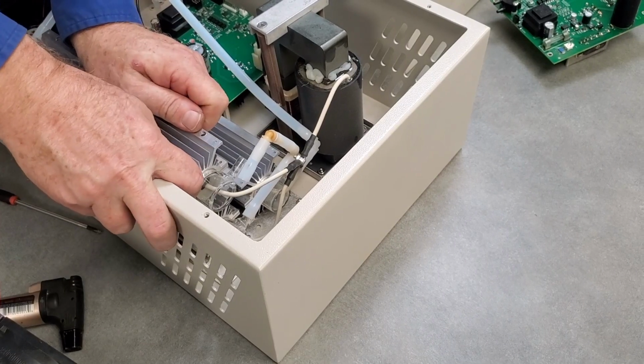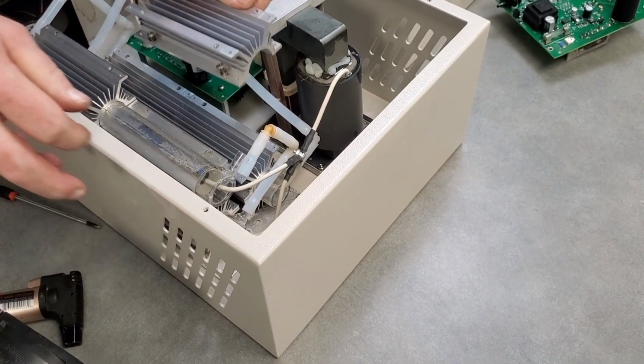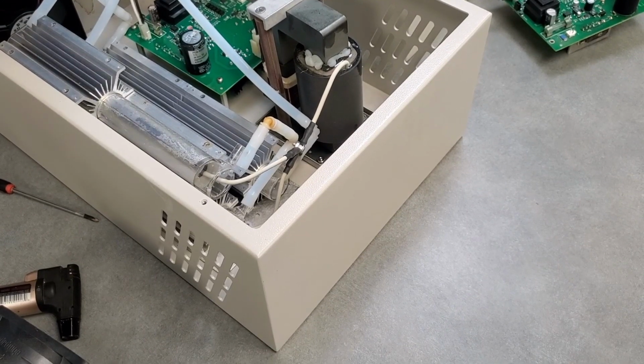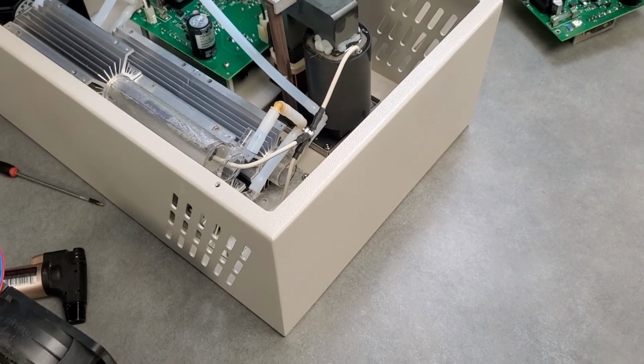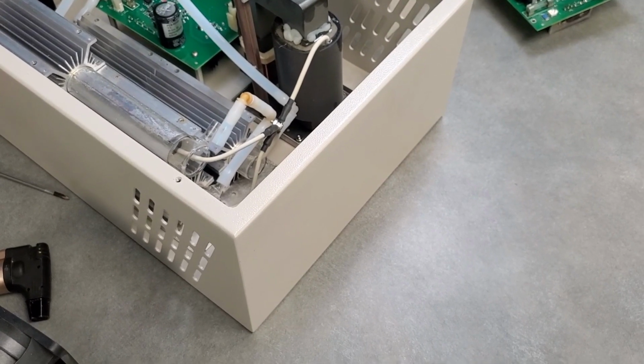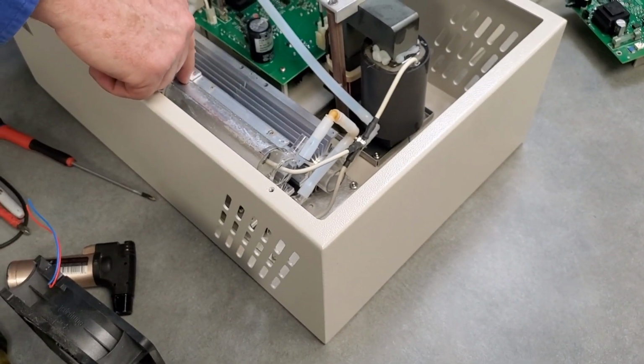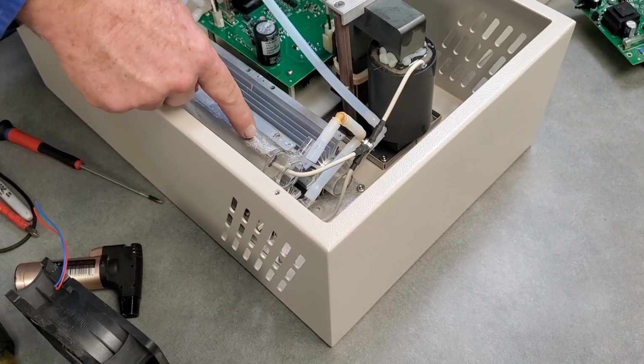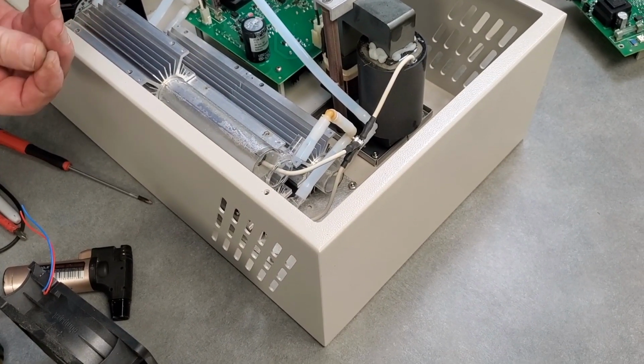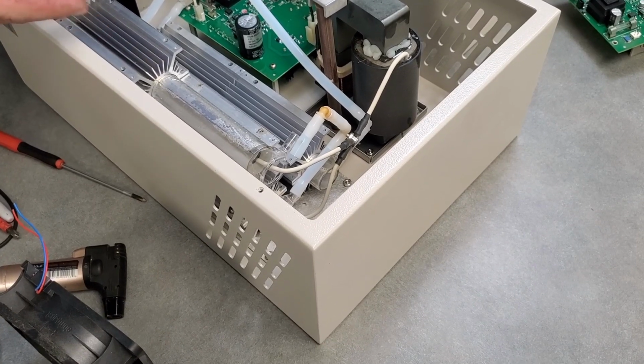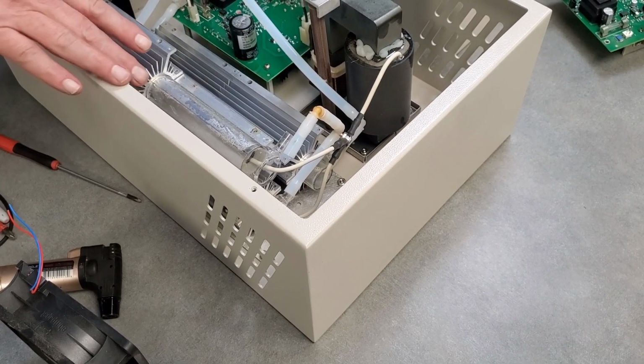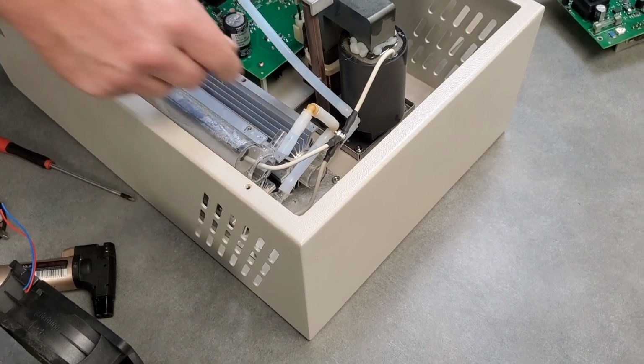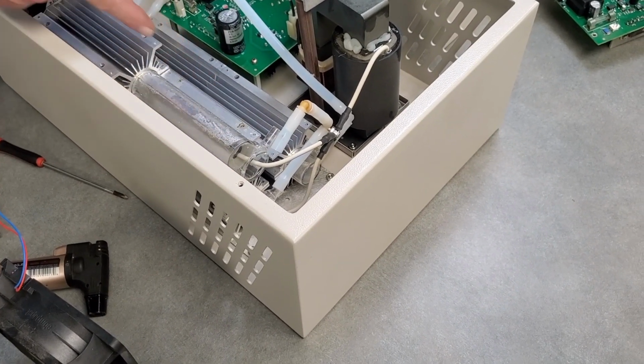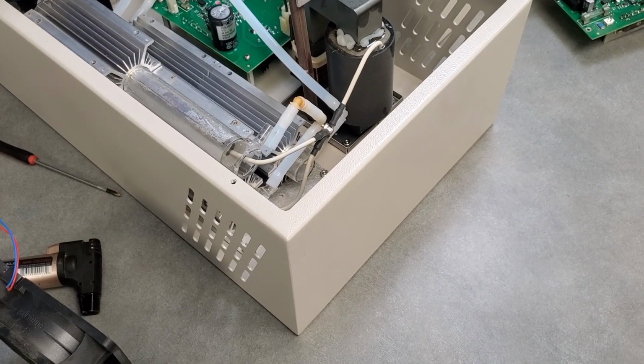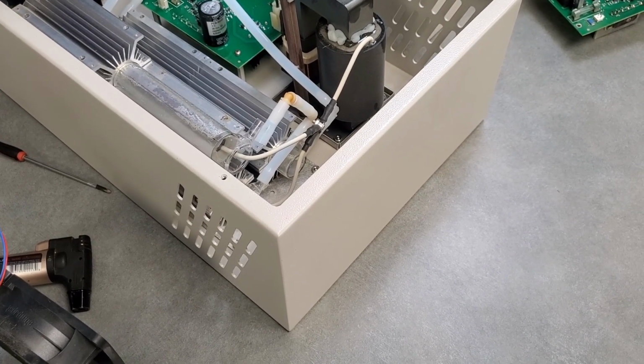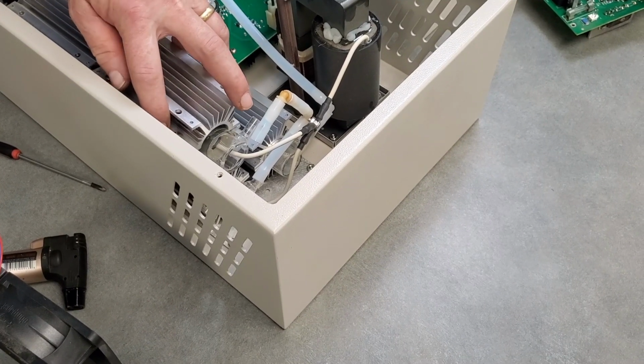Okay, so we got the screws out. This just got really hot, and it melted some of that, it's really not glue, but whatever is used. This is like an aluminum tape over the top, and then there's like an aluminum heat sink material. You take both of them off, and this whole tube will come out and can be replaced. There's a little bit of a gap, and it's smart to put just a little dab of heat sink paste, so that you've got good contact.